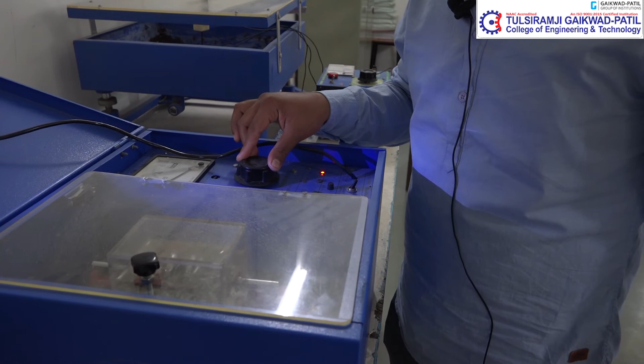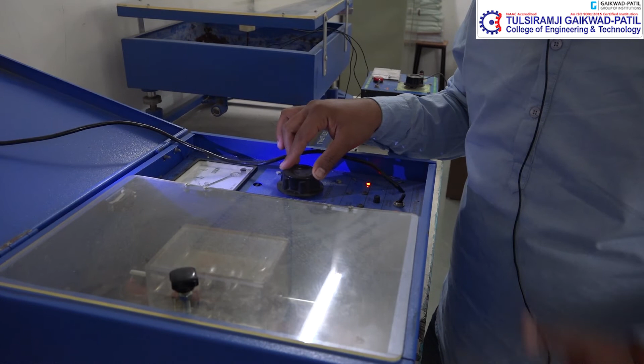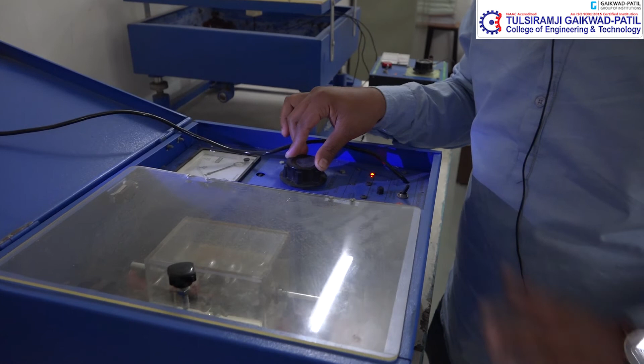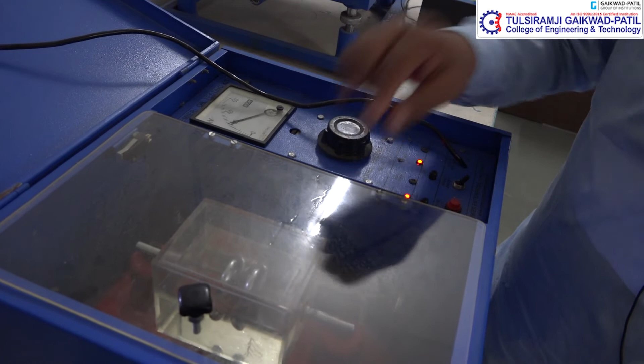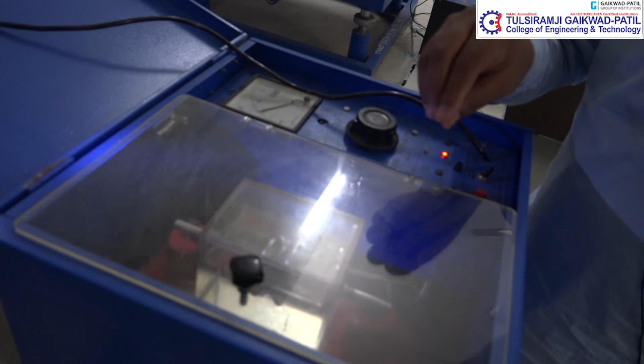Raising the voltage, up to some voltage there will be a spark in this transformer oil. That we have to note, and that is the dielectric strength or disruptive voltage of the transformer oil, this many kV. Now it is 20 kilovolts. Still there is no spark in this setup. At 22 kilovolts we have seen a spark in this transformer oil. It means the dielectric strength of this transformer oil is 22 kV, beyond which it will not act as an insulator. This way we have completed this experiment.